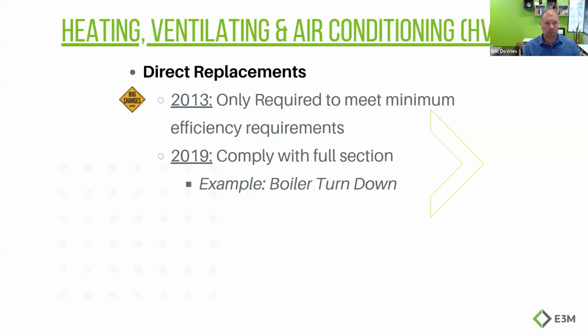You just had to meet a minimum equipment efficiency. What has changed in the 2019 code is now you must comply with a full section. So if you take a 5-ton rooftop off of the roof of a building and you're putting a 5-ton rooftop back, that 5-ton rooftop now not only has to meet the minimum efficiency, but it's got to have low leak dampers, it's got to have an economizer, it's got to have CO2 controls if it's a certain type of space. A lot of the bells and whistles that you could get around under the current 2013 code when you were doing a one-for-one replacement, you can't now. You have to add those things.